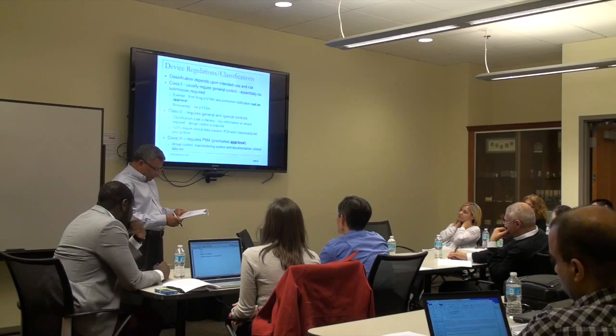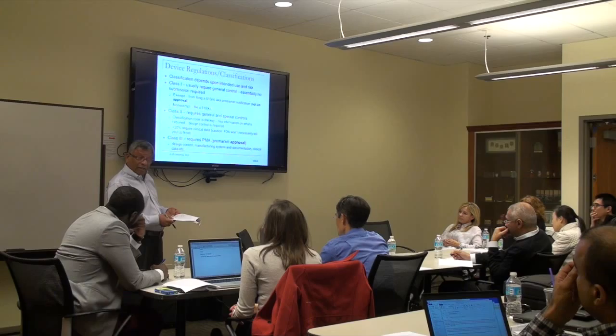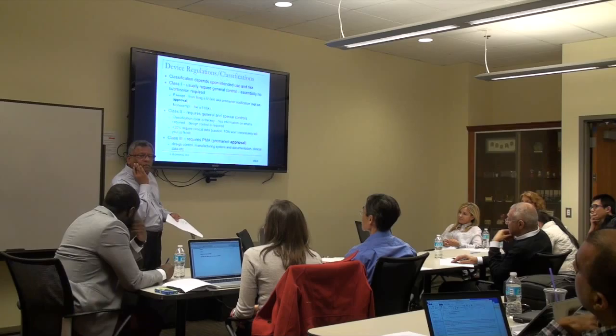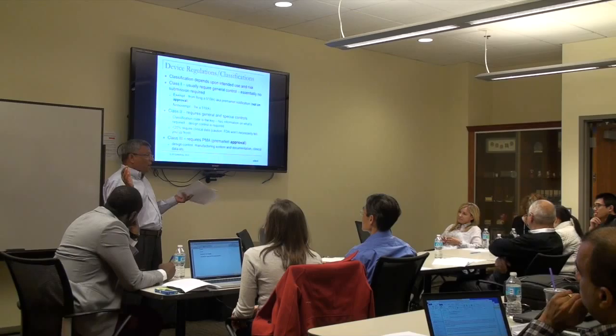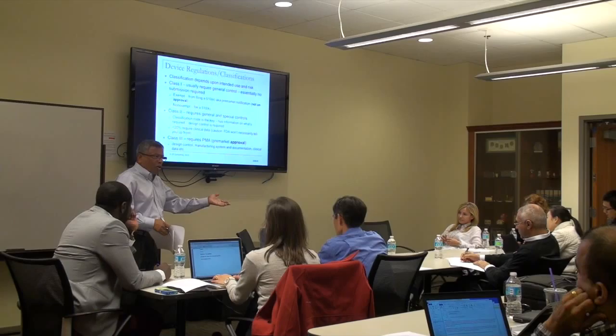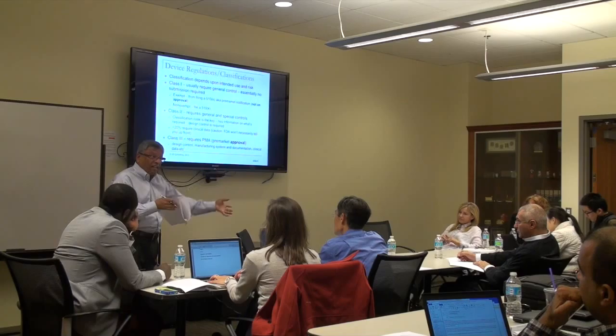Class 3. Less than 20% of devices require clinical data for their submission. There's a gotcha here: FDA won't explicitly tell you they want clinical data. They'll say 'it would be nice to have some clinical data' — and then you're behind the eight ball. Some regulations do specify it for certain devices, so you know upfront. That's where IDE — Investigational Device Exemption — comes in. I can only put a product on a human being if it's approved for sale, so experimental devices require an IDE. Typical numbers are around 30 to 50 patients for device submissions.